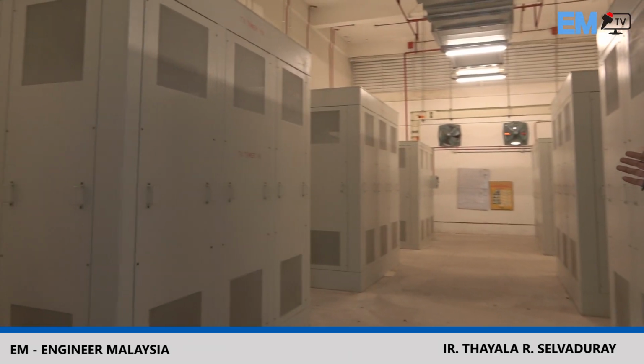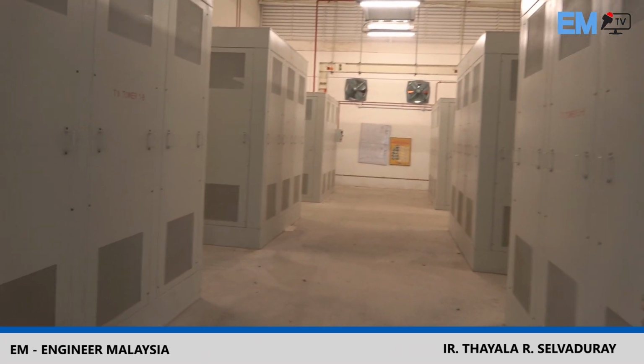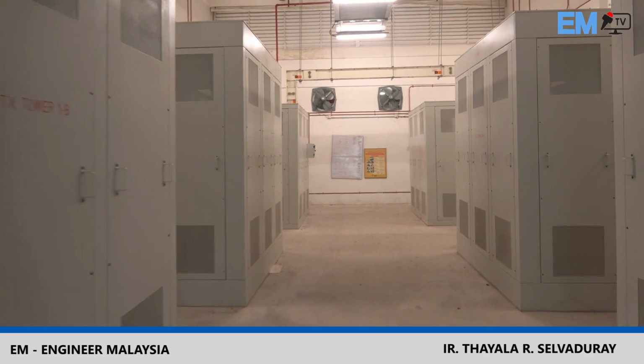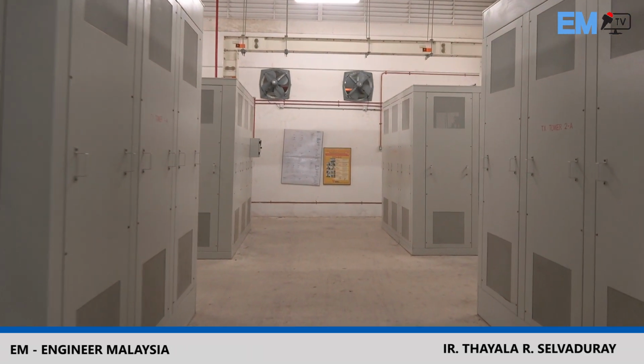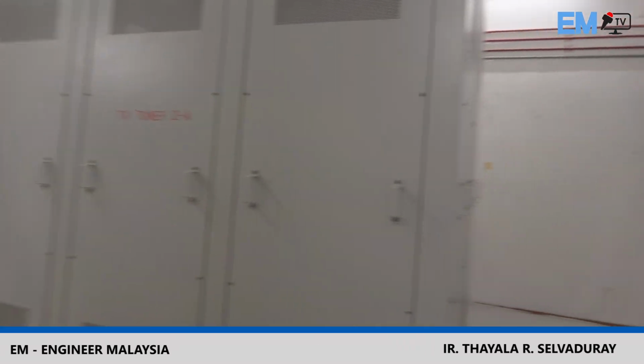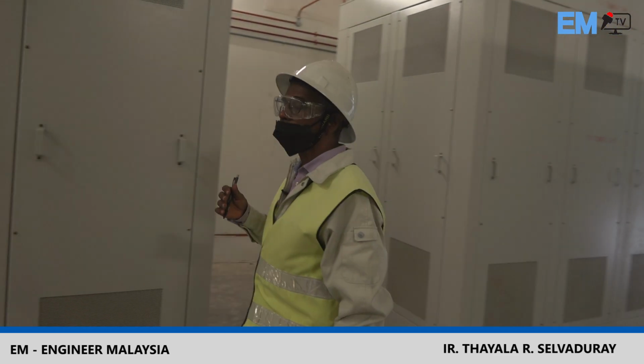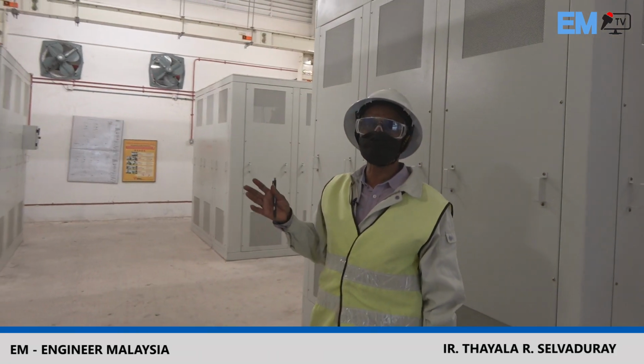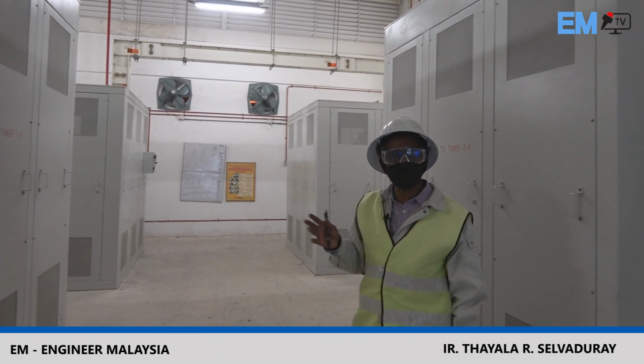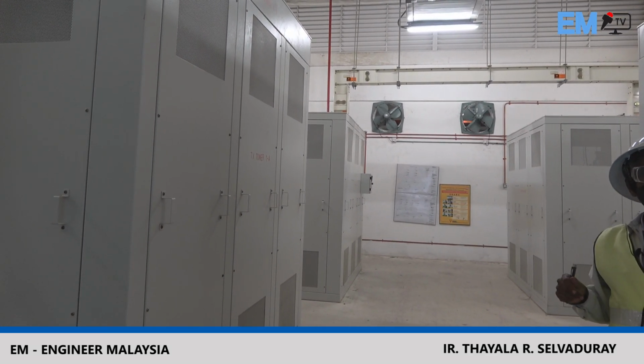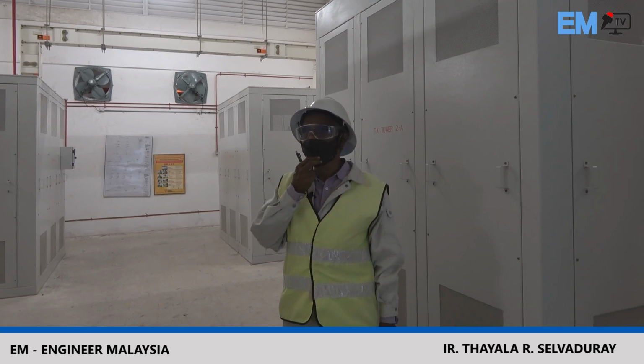Let's go inside. So what you see here is 6 transformers. They work 24/7, and technically speaking you can isolate some of these transformers to save some energy. So you have got 6 transformers. Should we use all 6 transformers? If you notice in the power supply, the current is very low. When the current is very low, the transformers are not delivering as they're designed for. So I would recommend for the management to couple the transformers, couple the switchboards and isolate the transformers. That way you can save, because these transformers are running 24/7 and there are losses in the transformers. This could be easily saved. Follow me please.